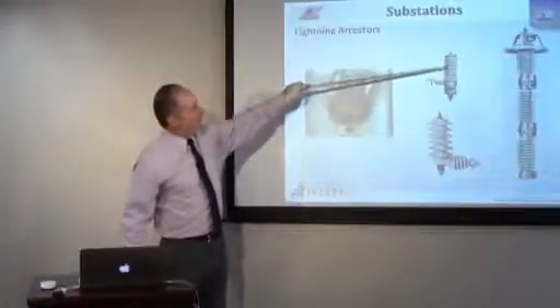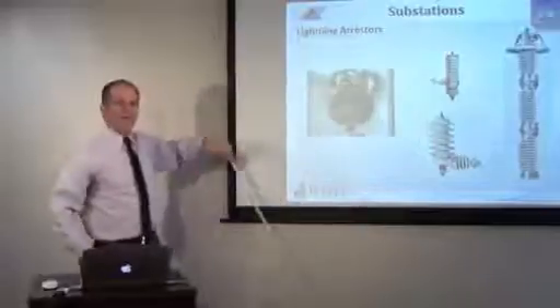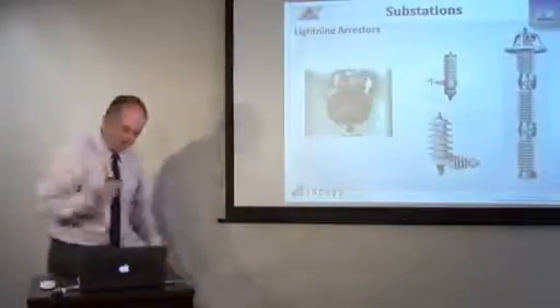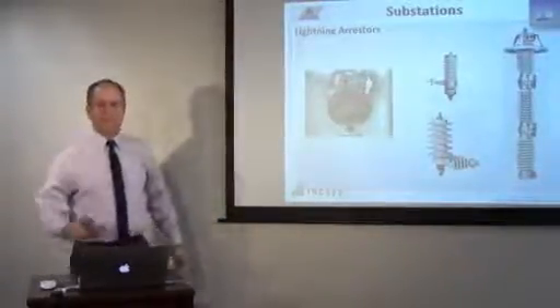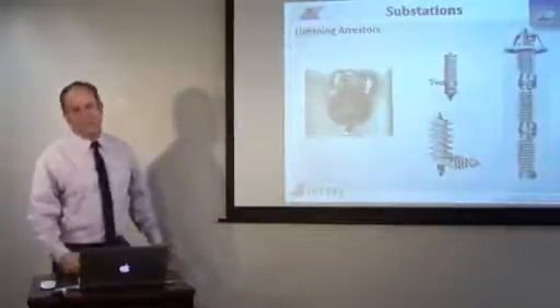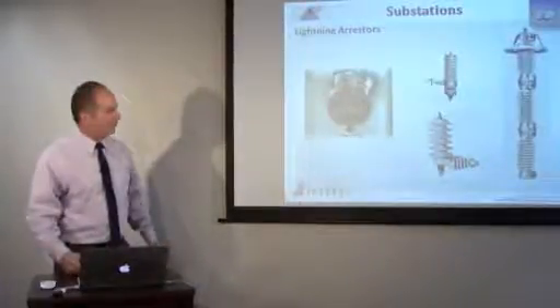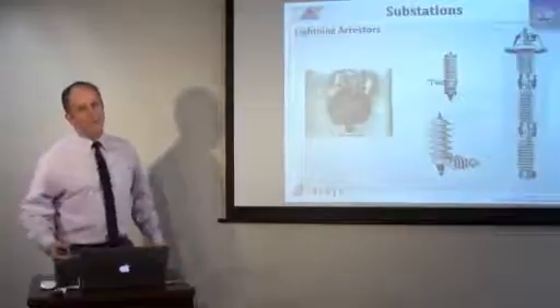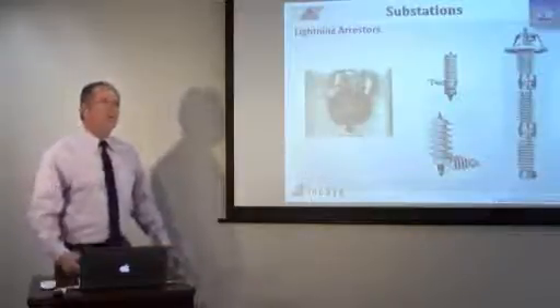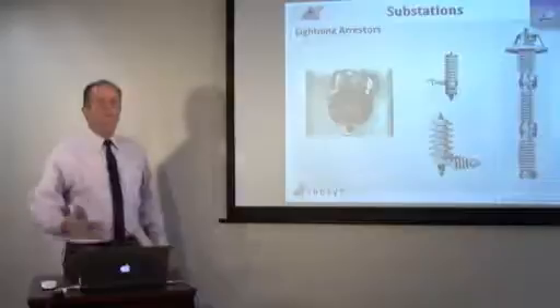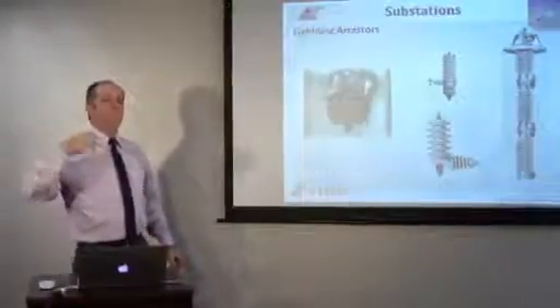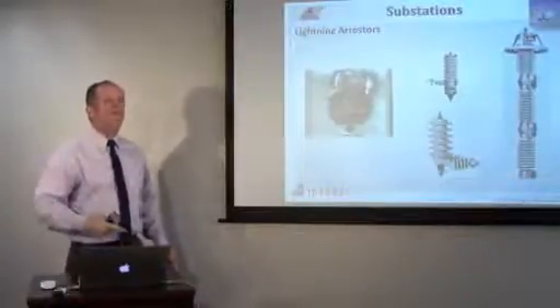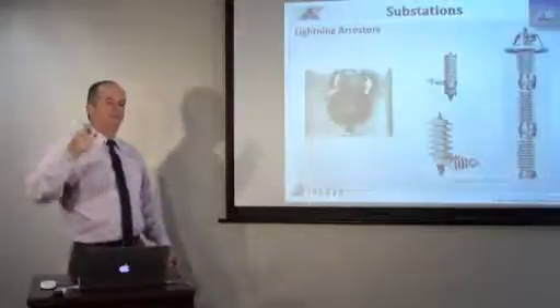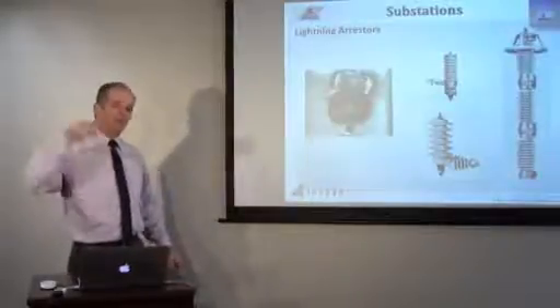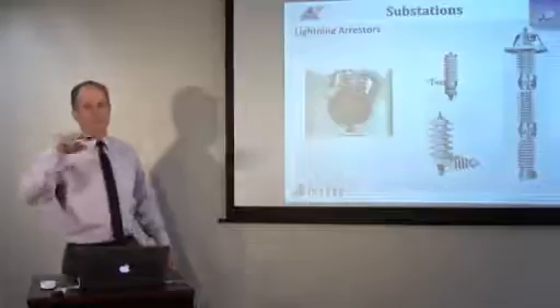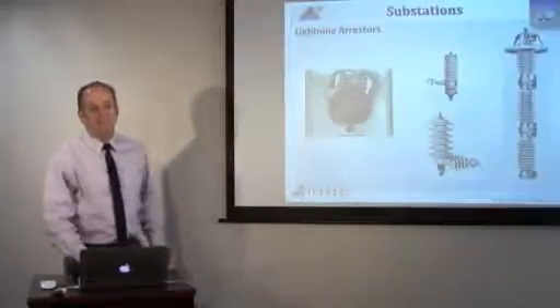So when the voltage got high enough, the air gap would close and the lightning arrestor would put a dead short right on the line and trip the breaker. And that's usually what happens. A lot of that still happens, even with the newer arrestors. But the newer arrestors are metal oxide, zinc oxide. They're a semiconductor. So when the voltage gets higher, the resistance starts to get lower. And then when the voltage gets too high, the resistance gets lower and current flows and actually limits the voltage, kind of like a clamping device.